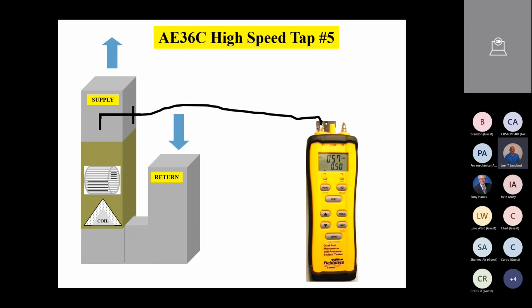Okay, let's do one more example of an air handler using the static pressure probe, and then we'll go ahead and jump into another method of measuring airflow, an older method called the temperature rise method, but let's do at least one more. And in this fourth example, we have an AE36C. So this is a 3-ton air handler, and it's also on high-speed tap.